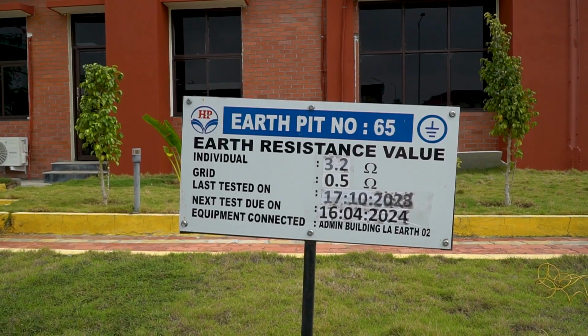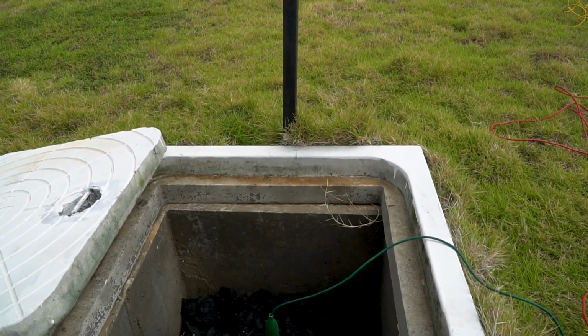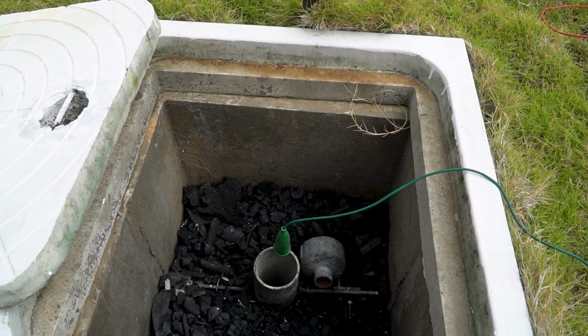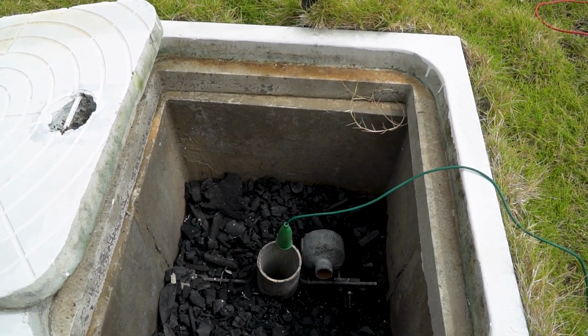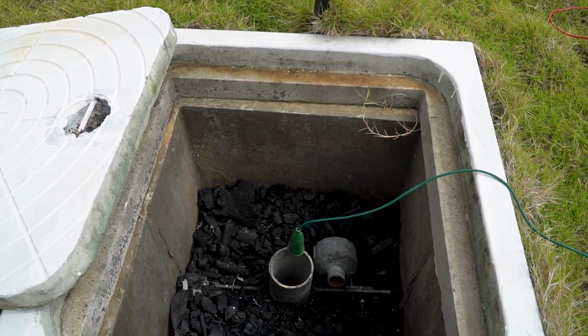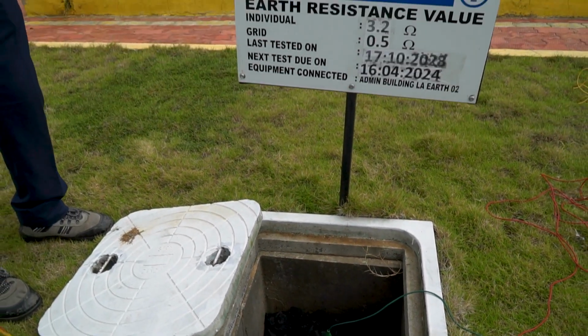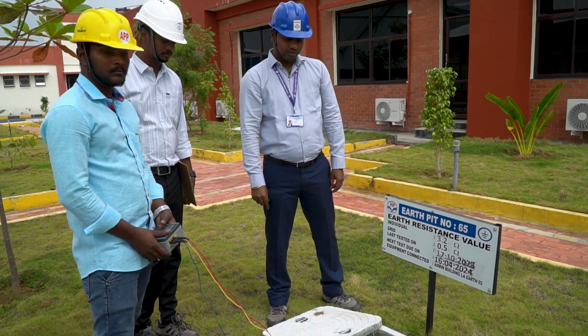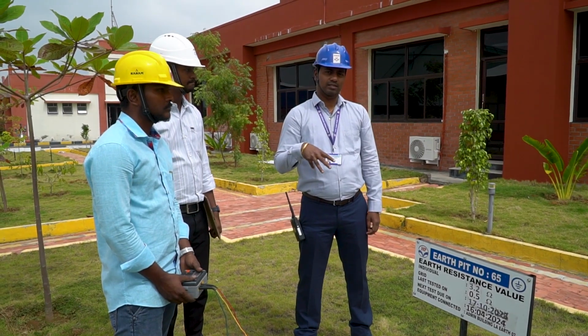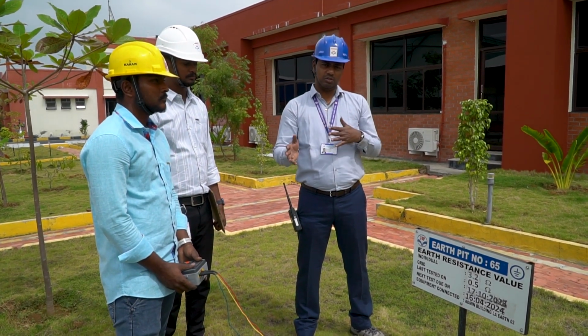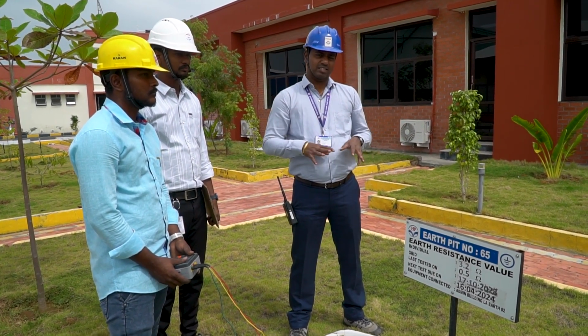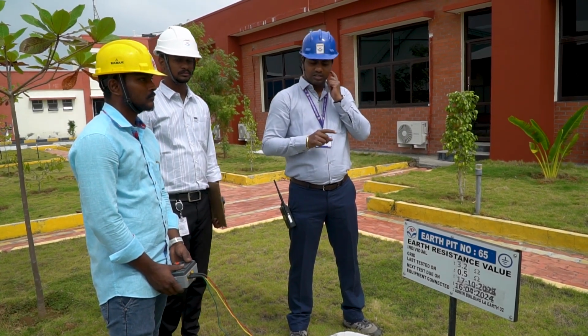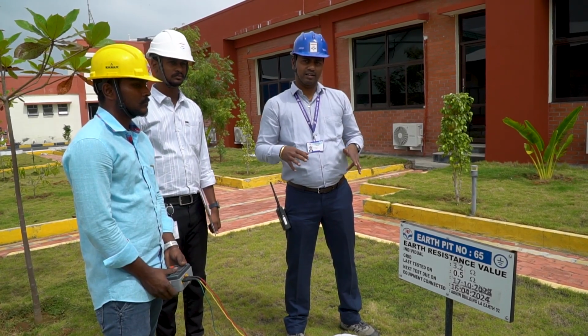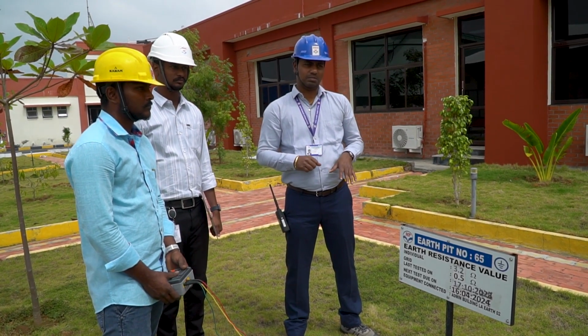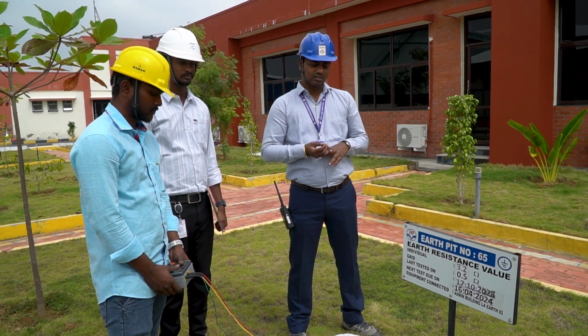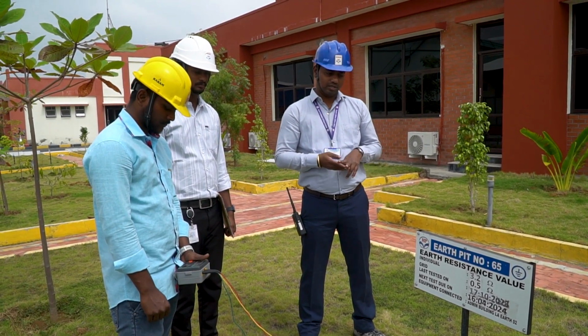If you see inside the earth pit, we have done the conditioning. Charcoal is put and watering is done. Salt is mixed with charcoal. So this earth pit is in good condition now. Once our values come, we are okay. For any earth pit, the value should be as per standard. We need to check both individual as well as grid values. Both ways it has to attain its desired value. If it is okay in grid but not okay individually, that earth pit is not accepted. For an individual earth pit, the value should come below 2.